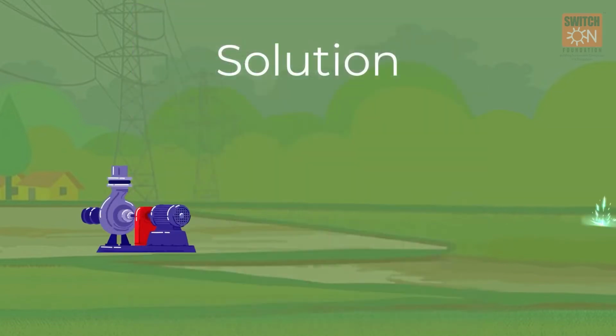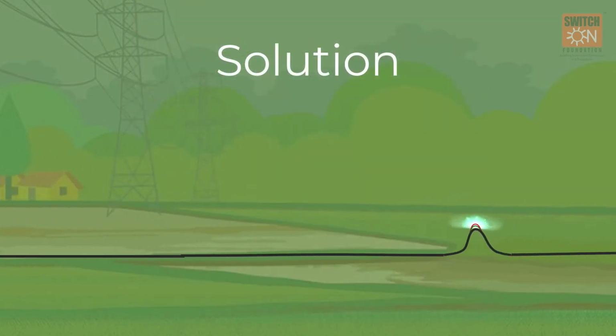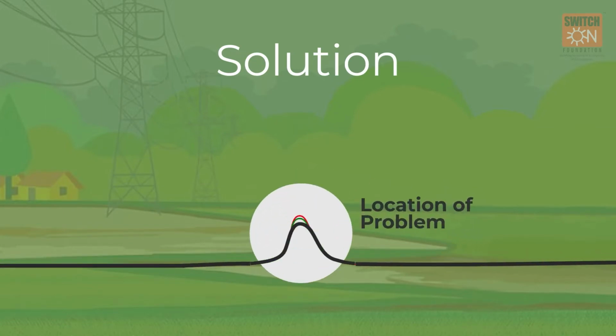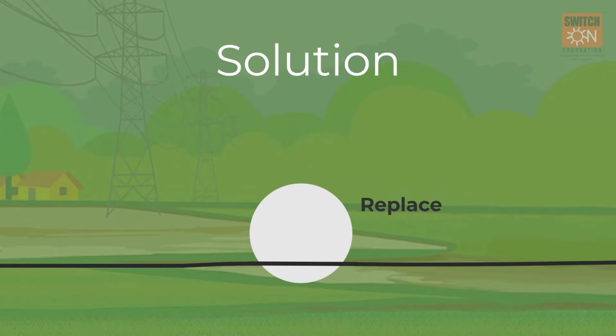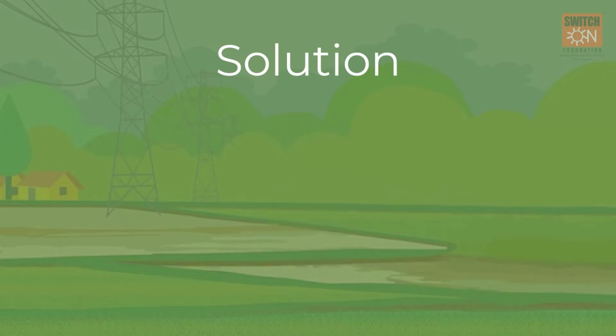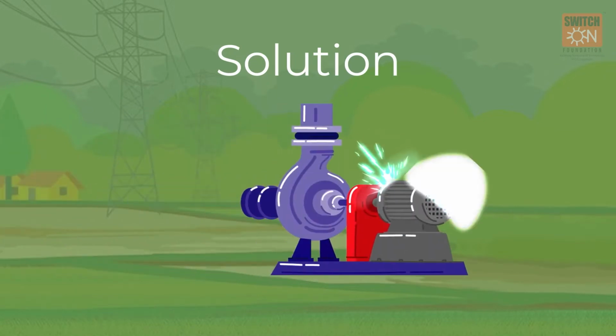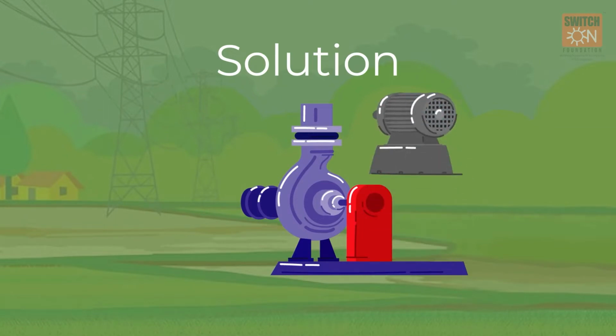Solution: firstly, the location of the short circuit needs to be identified. Then, the particular portion of the cable needs to be replaced with a new cable. If the short circuit happens in the winding of the motor coil, then the coil needs to be changed.